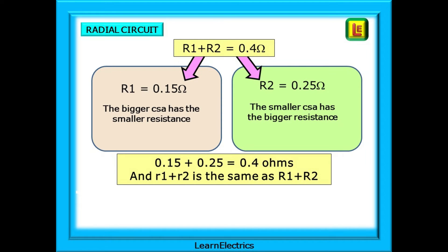R1 is the line, the bigger CSA, and this has the smaller resistance. The CPC, R2, has a smaller cross-sectional area and should have the bigger resistance. As this is a radial circuit, little r1 plus little r2 is the same as big r1 plus big r2.